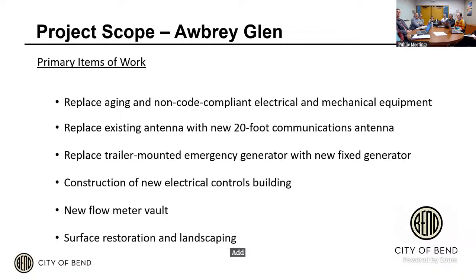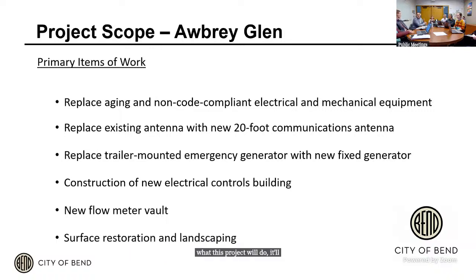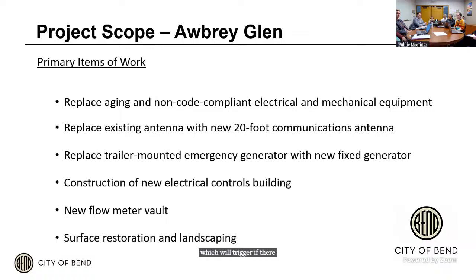Additionally, there's a trailer-mounted emergency generator on site. The issue is that if the power goes down in the pump station, someone has to go out there and actually start that generator for things to start moving again. This project will establish a permanent generator with an automatic transfer switch that will trigger if there's a problem with the power grid.